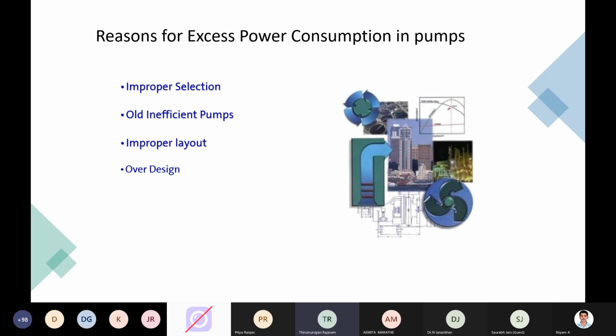And then improper layout. The layout also needs to be understood, because the pump is not just going to transfer water from point A to B. So we need to understand how the pipe routing is happening between point A and point B, and how much friction loss is coming into the picture. And second, the piping plays an important role in making the pump efficient to some extent, because when it gives an opportunity for air entry, obviously the pump will try to deliver both water and air to the source, and obviously the pump will not perform. So piping also plays a vital role here.